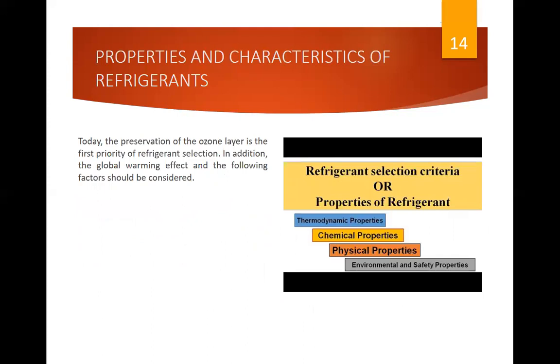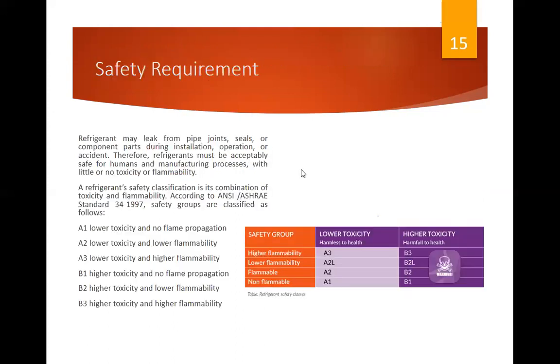Properties and characteristics of the refrigerants. So today, the preservation of the ozone layer is the first priority of refrigerant selection. In addition, the global warming effect and the following factors should be considered. Safety requirements. Refrigerant may leak from pipe joints, seals, or component parts during installation, operation, or accident. Therefore, refrigerant must be acceptably safe for humans and manufacturing processes, with little or no toxicity or flammability.